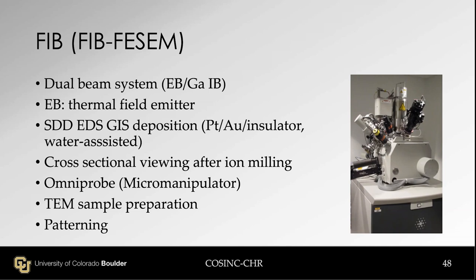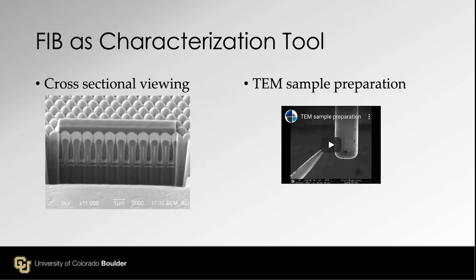It's very useful to do cross-sectional viewing after ion milling. An Omniprobe micromanipulator is attached, and this kind of instrument is very popular for TEM sample preparation, especially site-specific TEM sample prep, and also patterning. FIB is an extremely useful characterization tool for two reasons. One is you can create a cross-sectional wall and then check it with SEM. The left figure is an example. From the top you see spherical arrays, but you can check what's going on underneath.